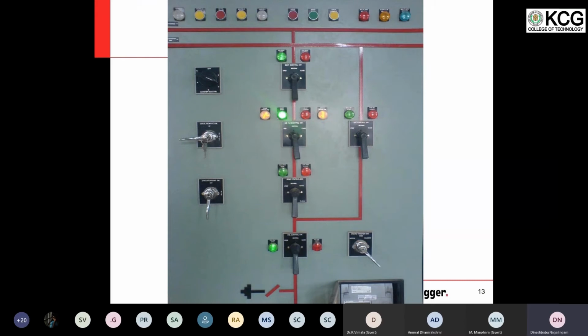The first story that we told was the interlock between the breaker and isolator. When the breaker is in closed condition, you cannot operate the isolator. Now, let us merge these things together and create a situation. So the situation is like this. Let us assume the isolator is open and the breaker is open. Now, someone standing in front of the panel knows this isolator is open and the breaker is open. He tries to close the isolator. Now the isolator takes 20 seconds to close. So it slowly moves along.